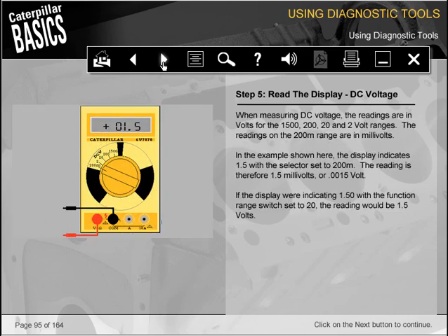When measuring DC voltage, the readings are in volts for the 1500, 200, 20, and 2 volt ranges. The readings on the 200m range are in millivolts. In the example shown here, the display indicates 1.5 with the selector set to 200m. The reading is therefore 1.5 millivolts or 0.0015 volt. If the display were indicating 1.50 with the function range switch set to 20, the reading would be 1.5 volts.